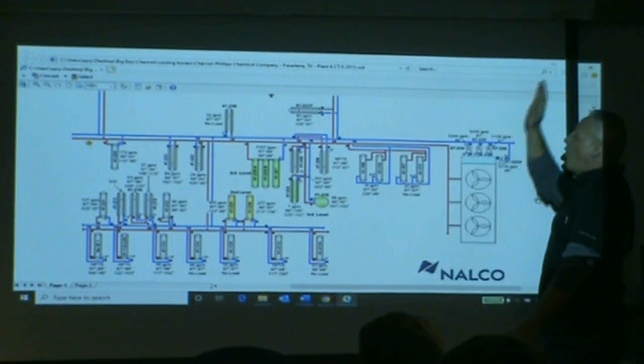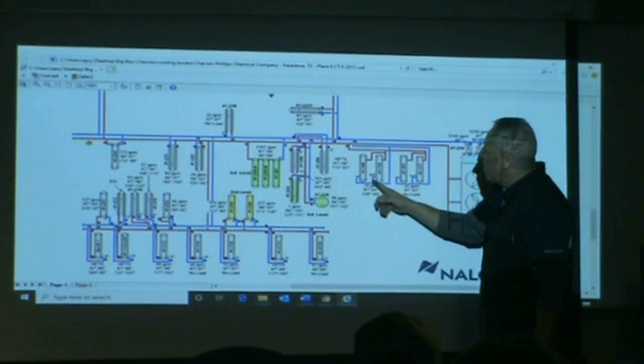You know how expensive that would be? The whole place would be down, because this is cooling tower water coming off these pumps, shooting out into the unit, coming in on the heat exchangers, and then coming back out as hot water.